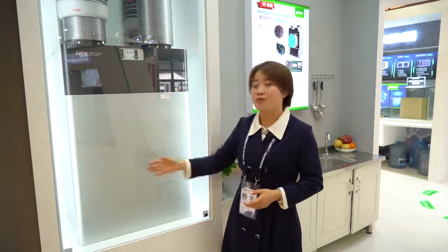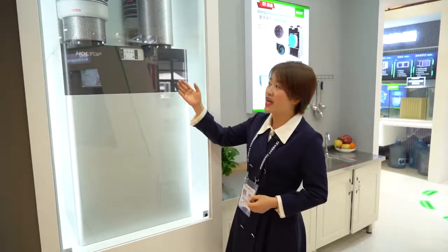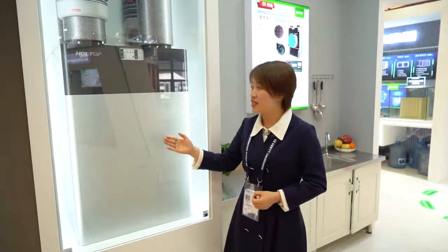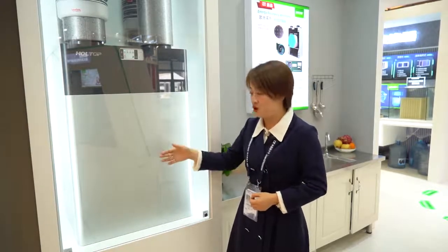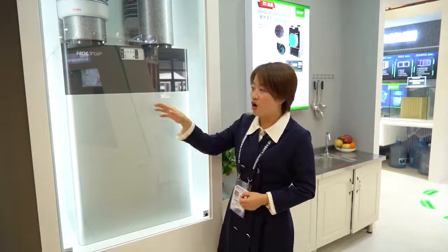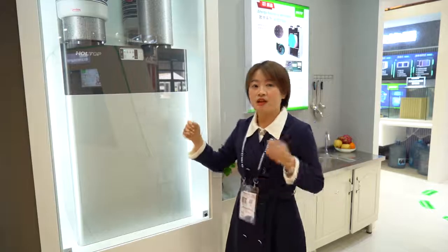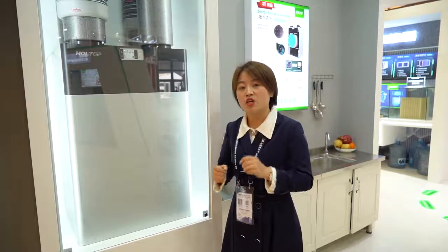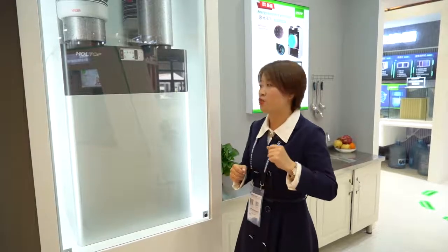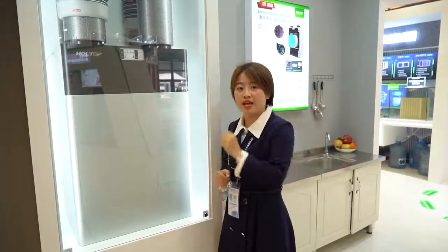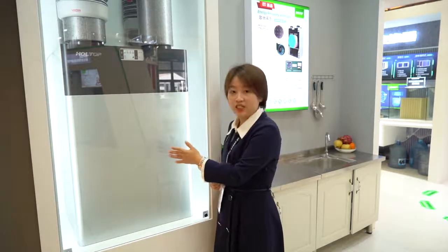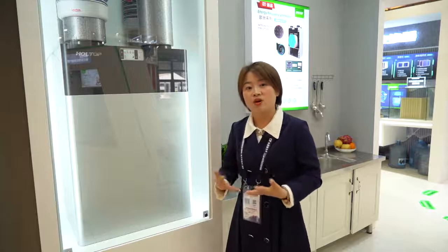Last but not least, some end users may worry about the maintenance of this unit. Well, for this HRV unit, the maintenance is very simple and convenient. What we need to do is just remove the access door. Then there is a C-pad behind this door. We just need to remove them. And then pull off the heat exchanger and the filters. Then use your normal vacuum machine to clean them. The last step is to put all these parts back in their positions and install them. Then put on the access doors, so everything is right. So it's very easy and convenient, right?